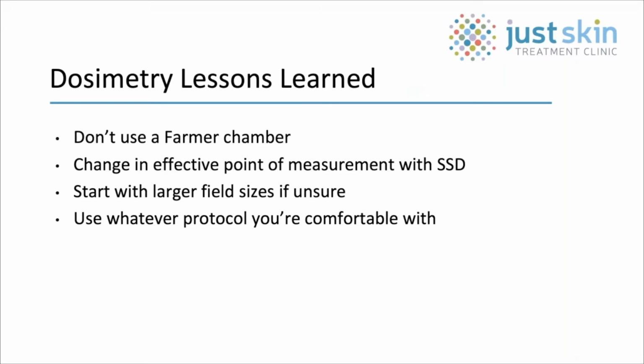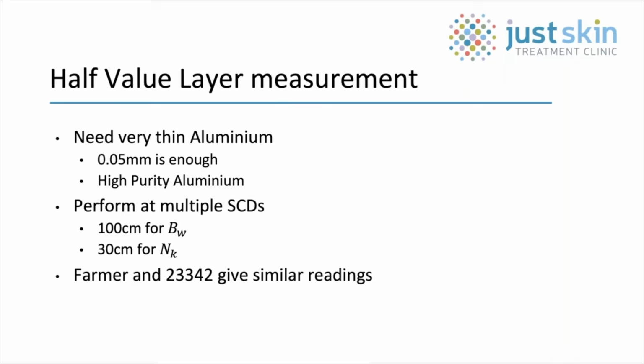I performed half-value layer measurements in the usual way. The only thing I did differently was that I performed the measurements at 2 different source to chamber distances. For higher energies, like 100 kV, each distance yields the same results. However, at these low energies, there is attenuation by air, so the distance matters. Because my ion chamber was calibrated at 30 centimeters, I used the 30 centimeter results to determine NK, and the 100 centimeter results for everything else.